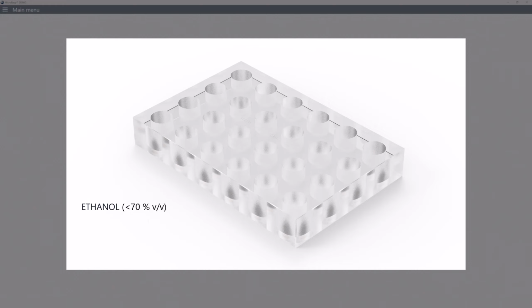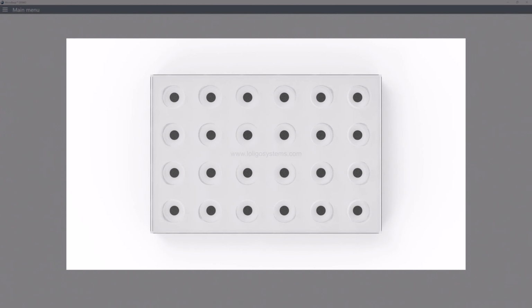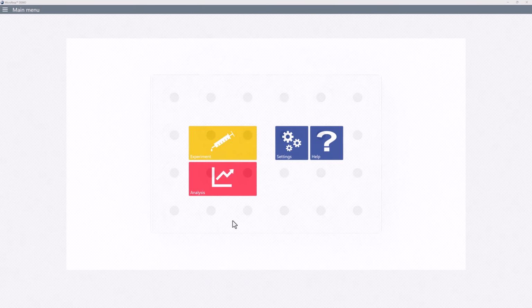If using ethanol to sterilize the wells, the oxygen sensor spots must dry out thoroughly for at least 2 days at 50 to 60 degrees Celsius in an oven to ensure that all alcohol residues have left the sensor dye matrix. We recommend performing a manual 2-point calibration after sterilizing.